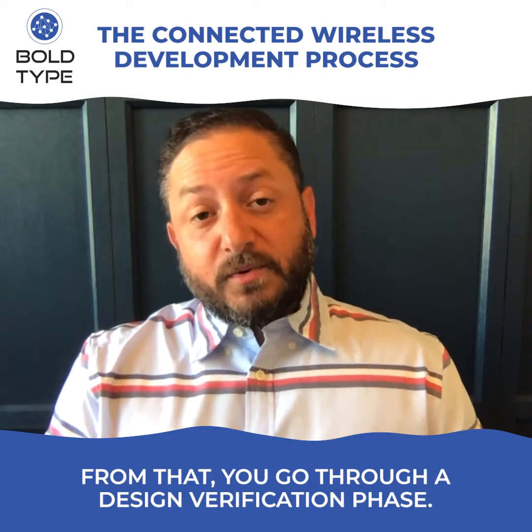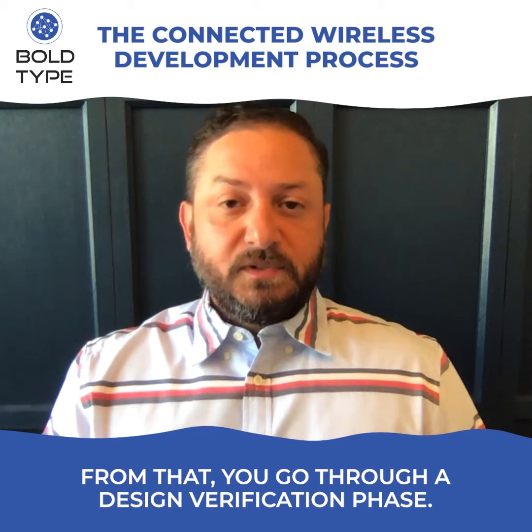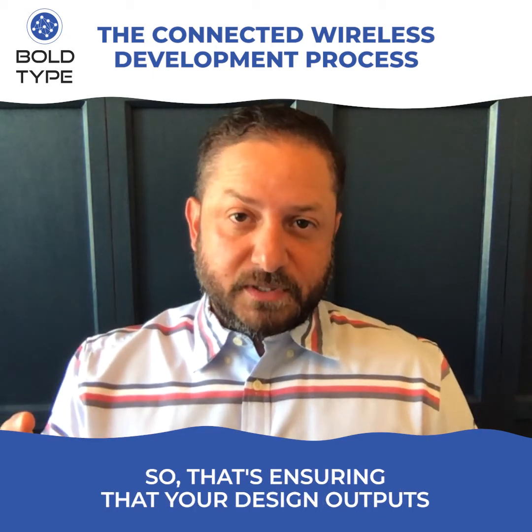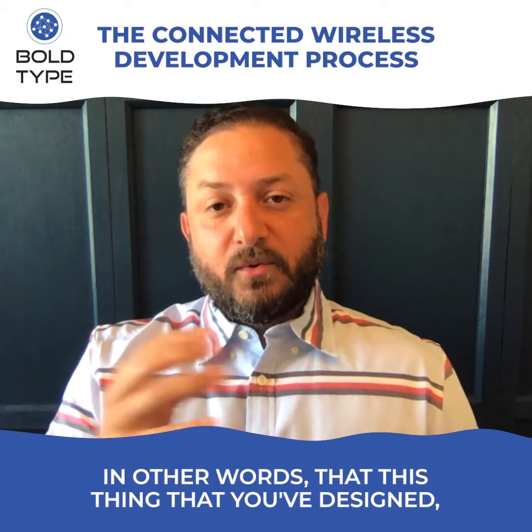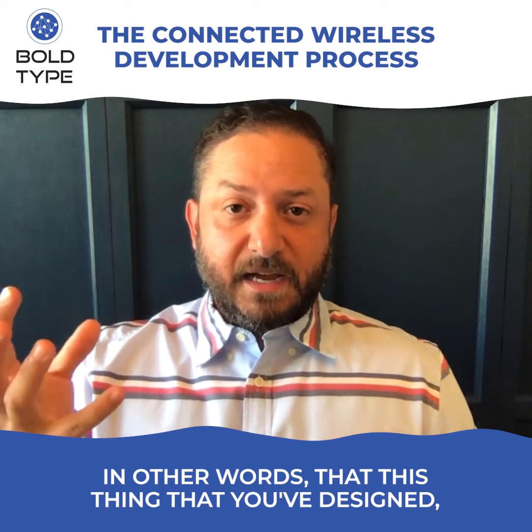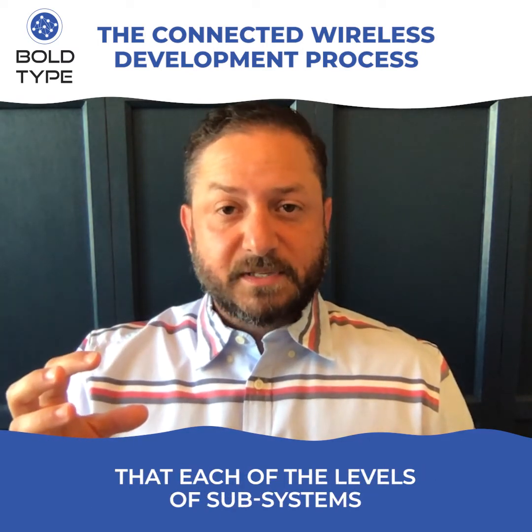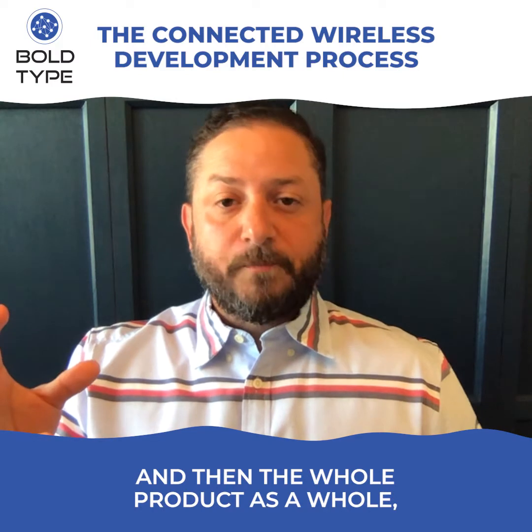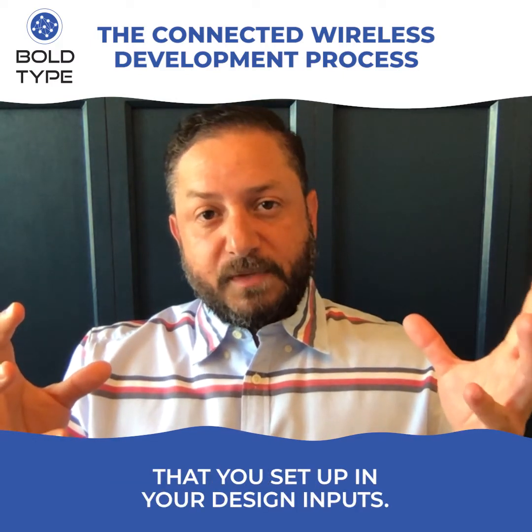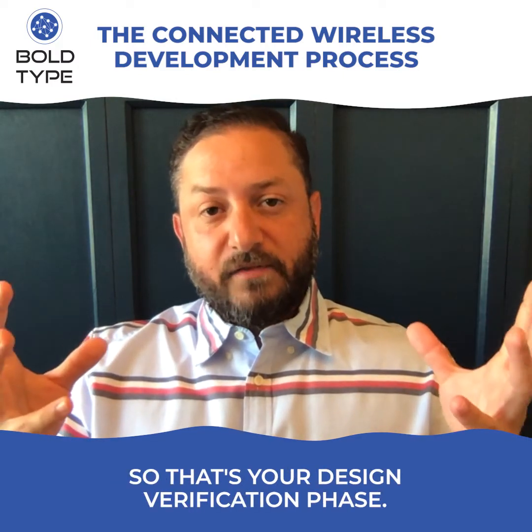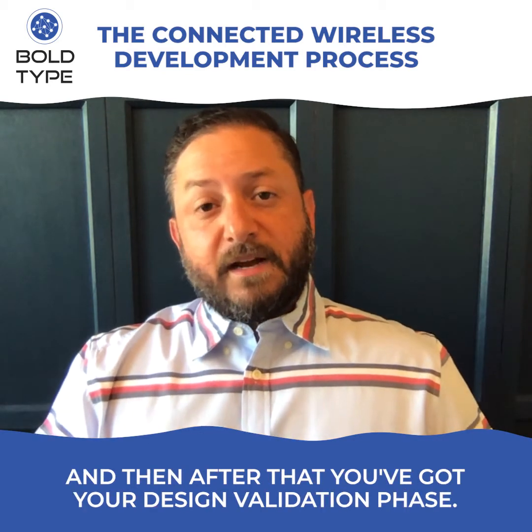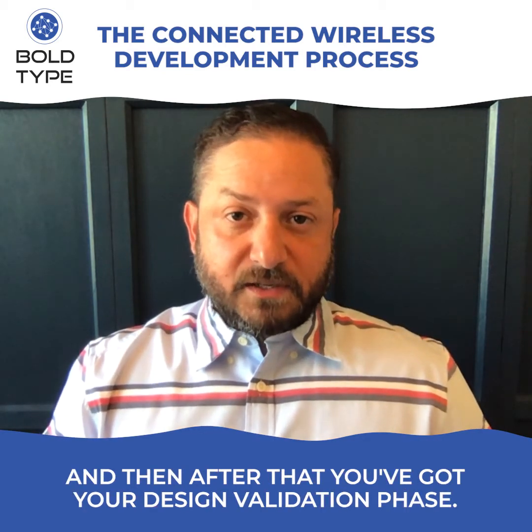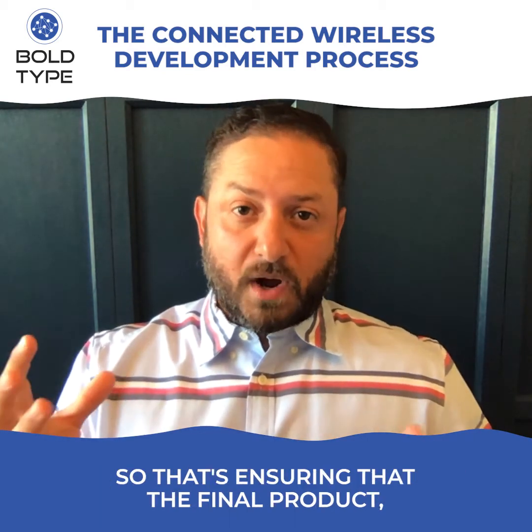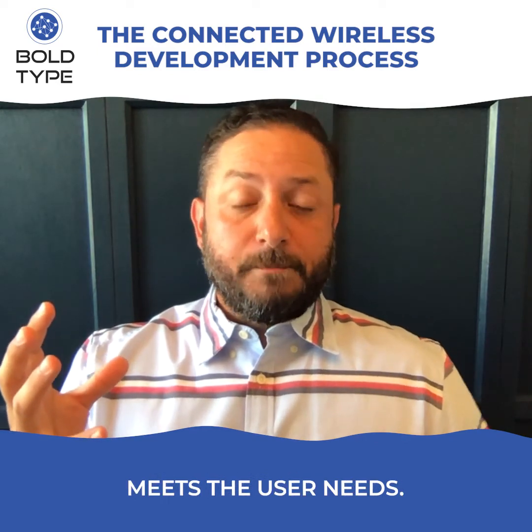From that, you go through a design verification phase. So that's ensuring that your design outputs meet your design inputs. In other words, that this thing that you've designed, that each of the levels of subsystems and then the whole product as a whole meets the requirements that you set up in your design inputs. So that's your design verification phase. And then after that, you've got your design validation phase. So that's ensuring that the final product, that the final design meets the user needs.